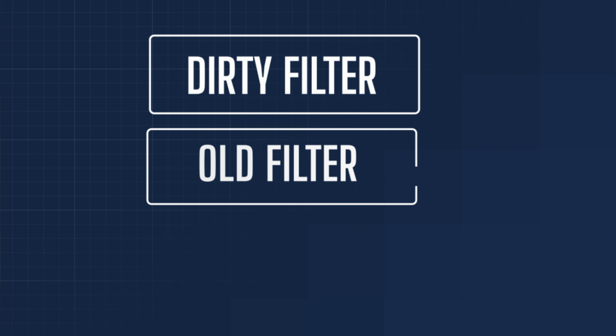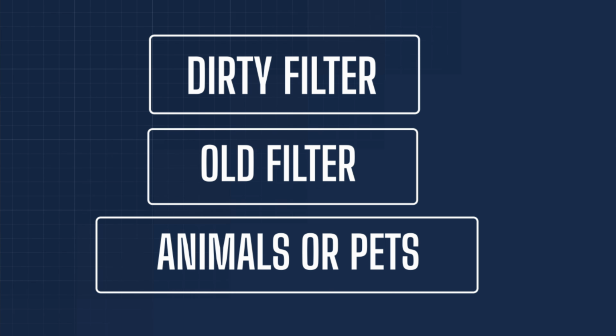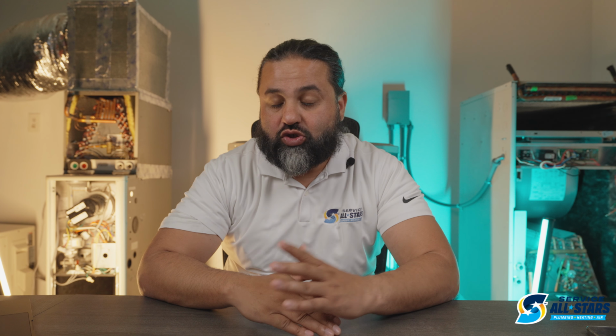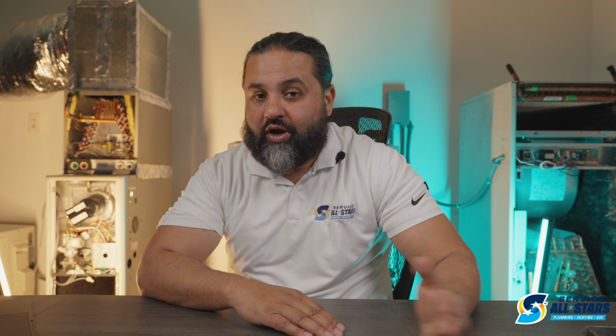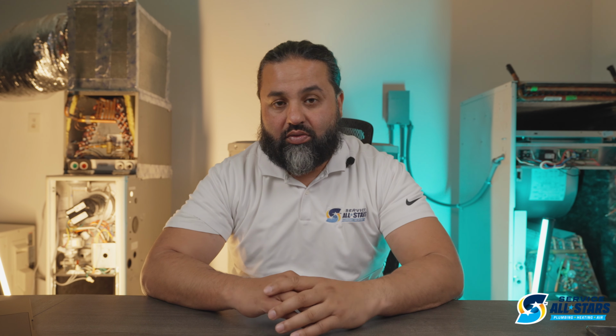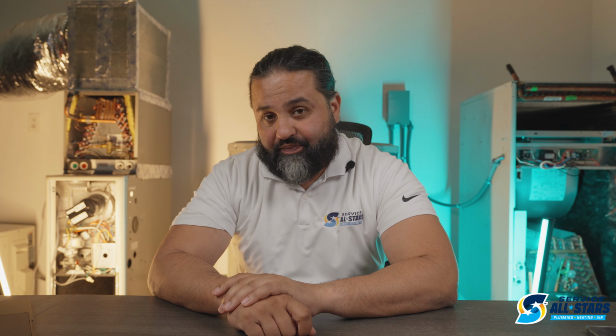So common causes of high static pressure could be a dirty filter, and people don't change their filter all the time. If you have pets, you should be changing your filter even more than normal. So one thing that static pressure also affects is your energy bills. If you have high static pressure, then your energy bills are going to be higher than normal. We really focus on making sure that the systems clients are buying, because a lot of clients, why do they buy new systems, right? It's to gain efficiency. The efficiency standard for SEER 2 right now is 14.3, and some clients of ours are buying 18 and 20 SEER systems. But just because you bought a system that should be operating at high efficiency, 18 or 20 SEER, doesn't mean that's what you're going to get out of it.